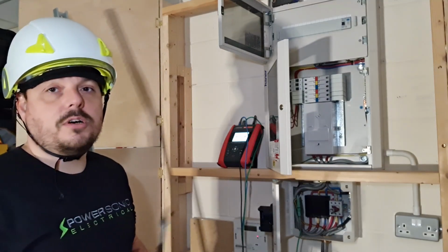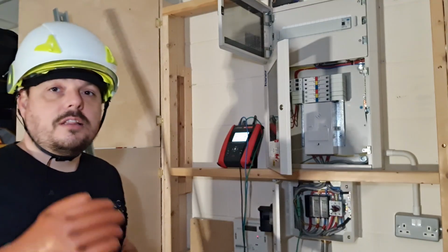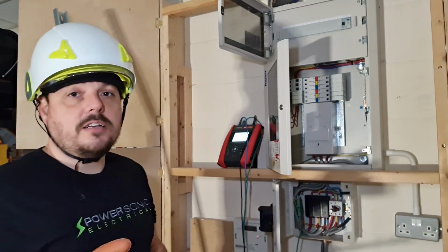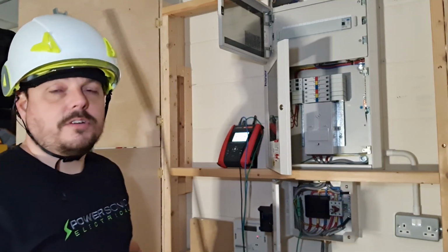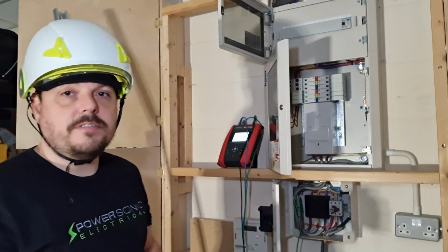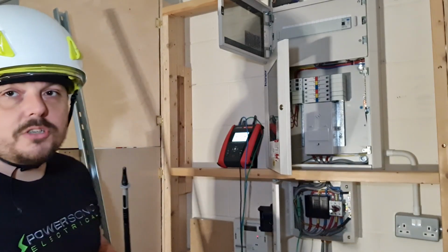bigger supply head with more current that was possible to cause an issue, then I would take appropriate measures with PPE. And if you are doing those kind of things, you really need to be getting an arc fault specialist to come in and do a calculation on the discharge energy that's going to be available at that point. But I'm all set up with this.